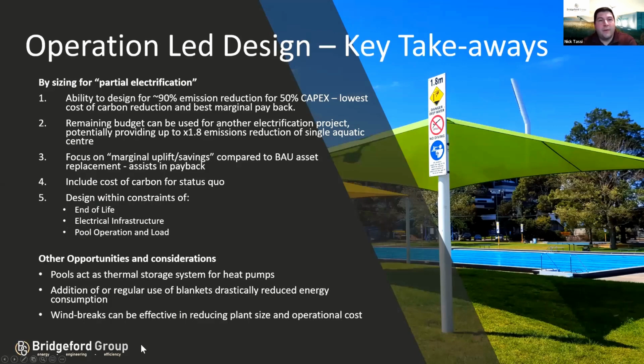So we've got a few key takeaways here, and we're terming this operation-led design. By sizing for partial electrification, you can put in a heat pump. It doesn't fully electrify the sites, but it's sizing it for, let's say, half capacity, 800 kilowatt instead of 1,600. You actually get close to 90% of the emissions reduction, because you're having those heat pumps run so many hours in the year, and the pools themselves are a bit like thermal storage tanks.